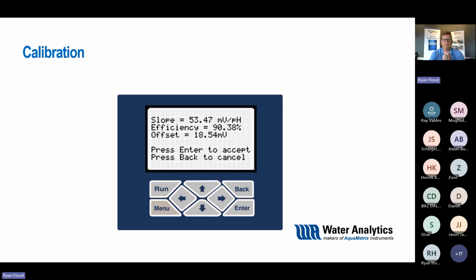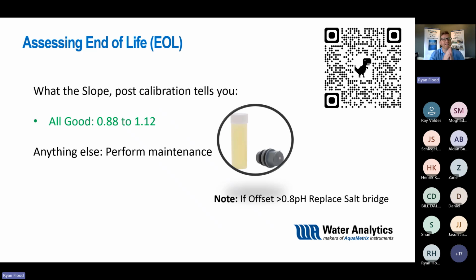But what it's giving you here is some information in front of you. And for those of you who have been in the industry for a while, this is probably familiar: your slope, your efficiency and your offset. Now, you can know what the slope is and what your ideal slope is supposed to be for millivolts per pH, but you don't need to know what the standard is. What you really want to know coming off of this are the numbers for efficiency and offset. These are really important numbers because they'll help you assess the health of your sensor. For the purpose of this, I'm going to go ahead and accept these. Then I'll talk about what this means by assessing the end of life of your sensor and determining when you need to perform more maintenance.